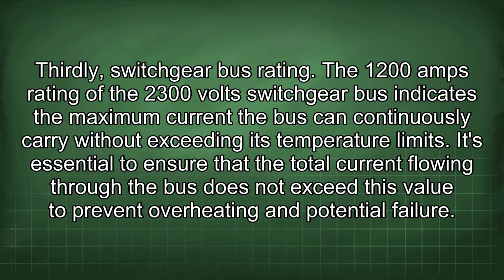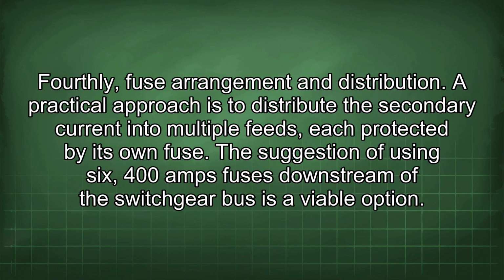Thirdly, switchgear bus rating. The 1200 amps rating of the 2300 volt switchgear bus indicates the maximum current the bus can continuously carry without exceeding its temperature limits. It's essential to ensure that the total current flowing through the bus does not exceed this value to prevent overheating and potential failure. Fourthly, fuse arrangement and distribution.